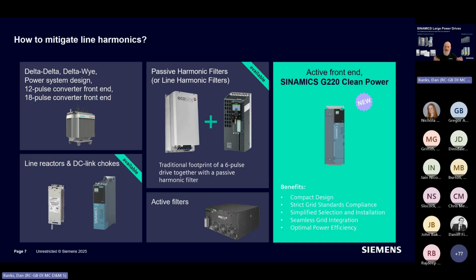So a standard drive would be a 6 pulse. There are 2 diodes on each phase, one for positive, one for negative. Double that up, put a transformer in front of it, and you get a 12 pulse converter. Pretty tidy, actually. Cuts your harmonic distortion down probably to about a third of what it would be before. Go beyond that and go to 18, 24, 36 even. That was the way these were addressed when you needed to do high power drives. But I would say, again, my opinion, that's kind of an old world technology. And the reason primarily for that is because of this lovely picture of a Siemens transformer on here.